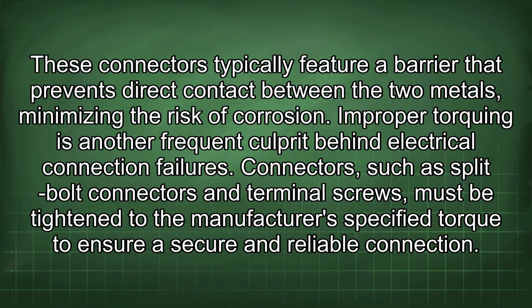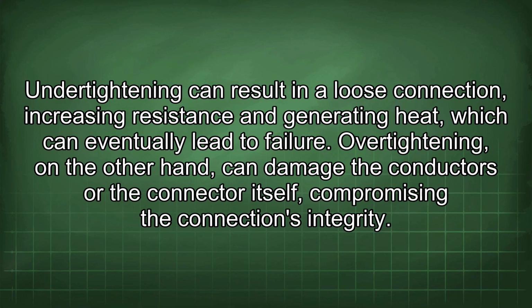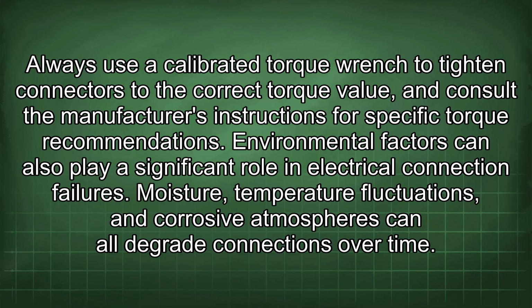Improper torquing is another frequent culprit behind electrical connection failures. Connectors, such as split bolt connectors and terminal screws, must be tightened to the manufacturer's specified torque to ensure a secure and reliable connection. Under-tightening can result in a loose connection, increasing resistance and generating heat, which can eventually lead to failure. Over-tightening, on the other hand, can damage the conductors or the connector itself, compromising the connection's integrity.